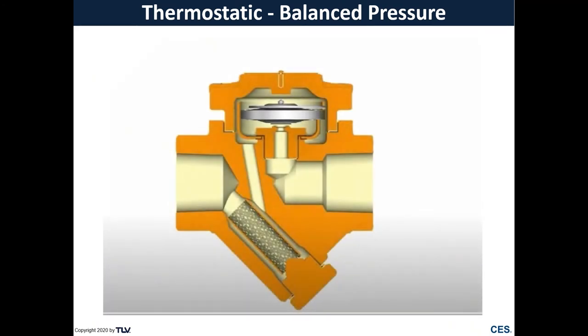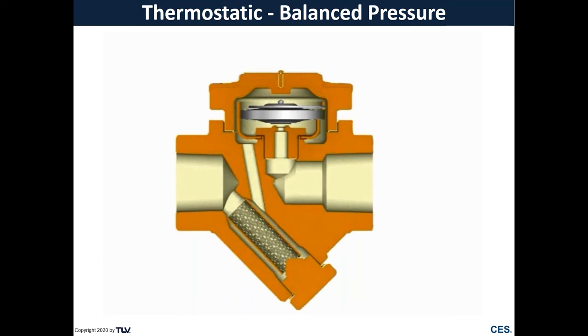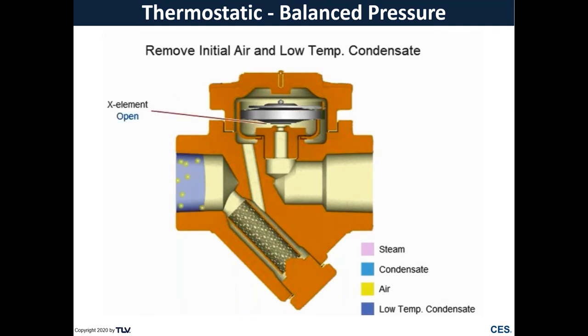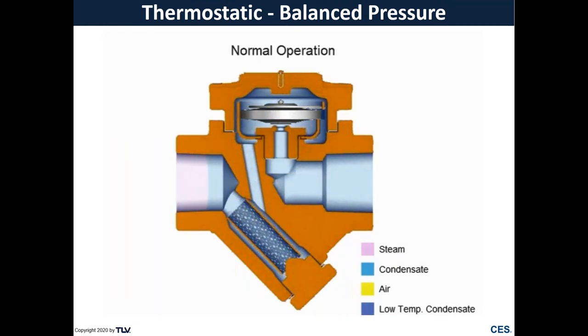This animation will take a look at what that looks like during operation. During startup, your system is going to be full of air and cold condensate. As that air and cold condensate begins to enter the steam trap, it won't have the thermal energy to vaporize that thermal liquid. So at this point, the trap is going to remain open and vent out any air and cold condensate. As the system starts to heat up, we get closer to steam, which is going to vaporize that thermal liquid, shutting the trap. And the condensate surrounding the X element will need to subcool for the trap to reopen. That's how this trap will begin to cycle.